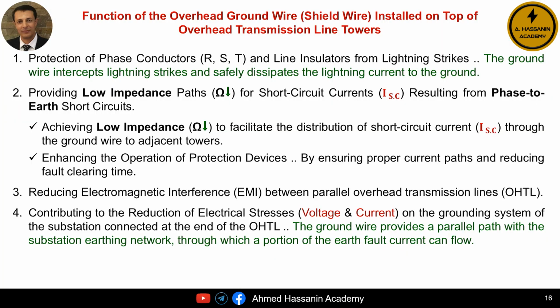The fourth function of the shield wire or earth wire or ground wire is to reduce electrical stresses, meaning the stresses caused by voltage and electrical current on the earthing system of the substation located at the end of the transmission line. Based on the same concept mentioned in point number 2, we find that the shield wire acts as a parallel path to the earthing system of the substation. Since the shield wire is connected in parallel with the earthing system of the substation, a portion of the earth fault current occurring inside the substation will pass through the shield wire. Consequently, the earth fault currents inside the substation will somewhat decrease. As these currents decrease, any electrical stresses, whether voltage or current, caused by earth fault currents will also decrease within the substation.